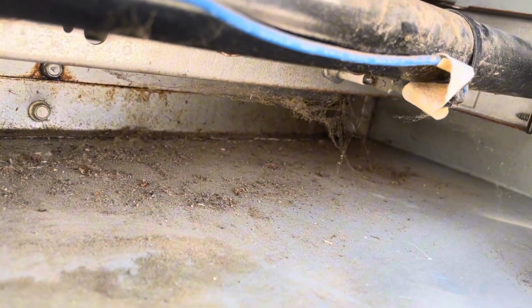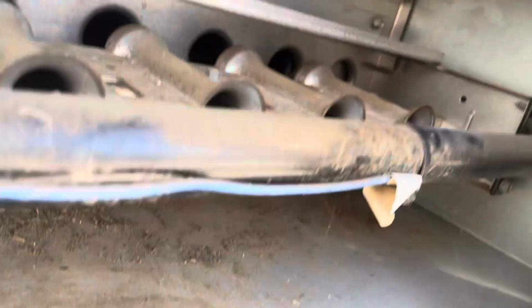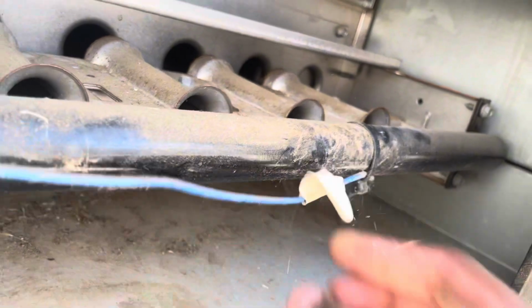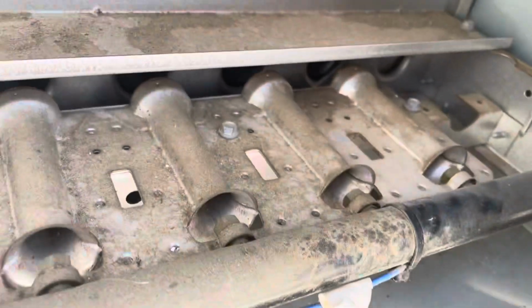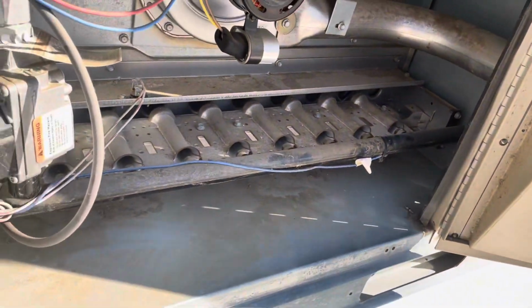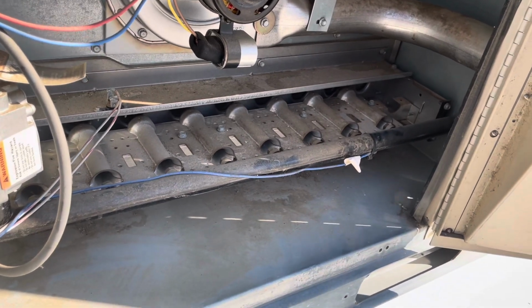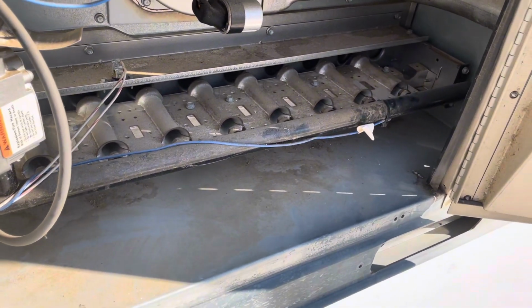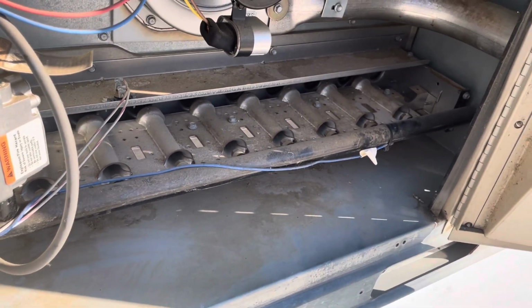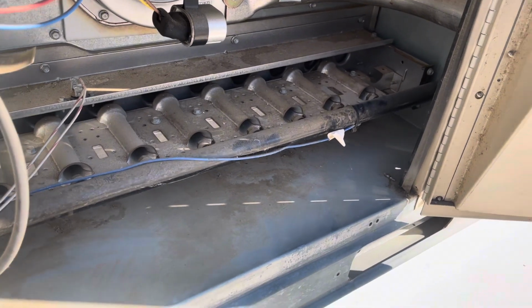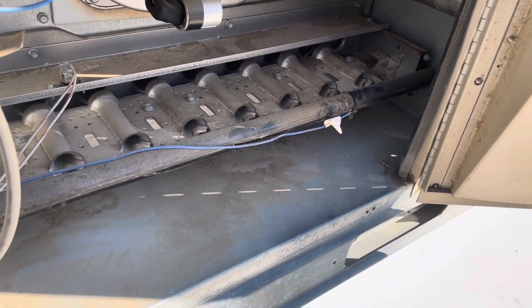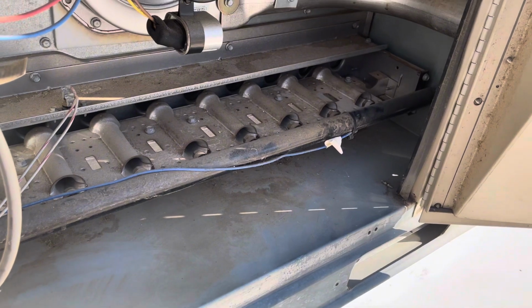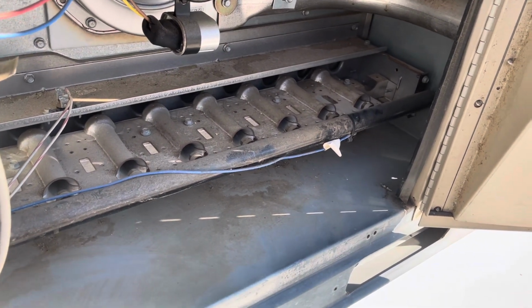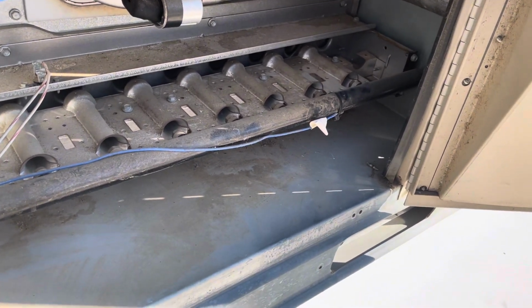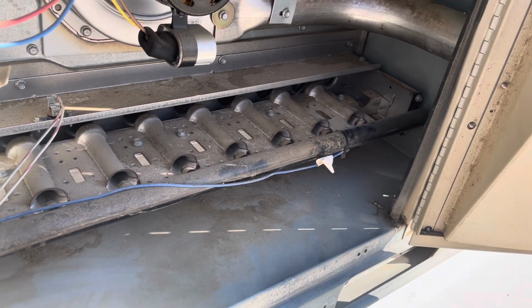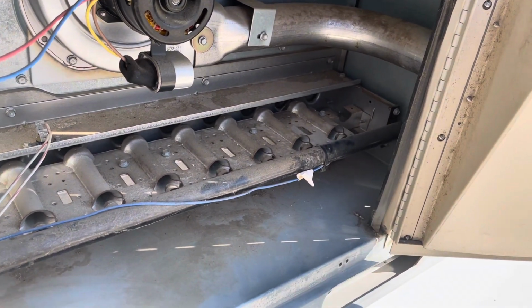All right, again, that's the flame sensor. Also check the wiring here, make sure it's tight. You can also check flame sensors while the whole system is running via DC microamps. Again, the flame is carrying current, although it doesn't conduct electricity very well. It doesn't carry the current very well, so the amp draw is extremely small.